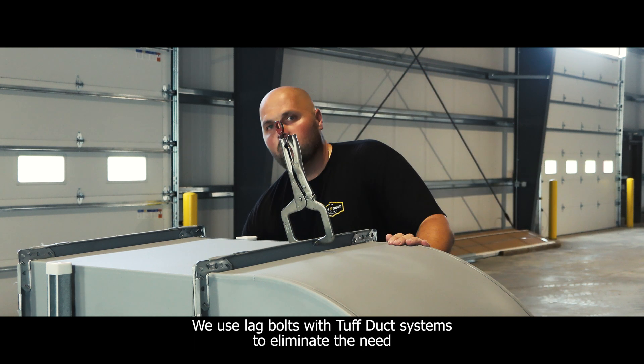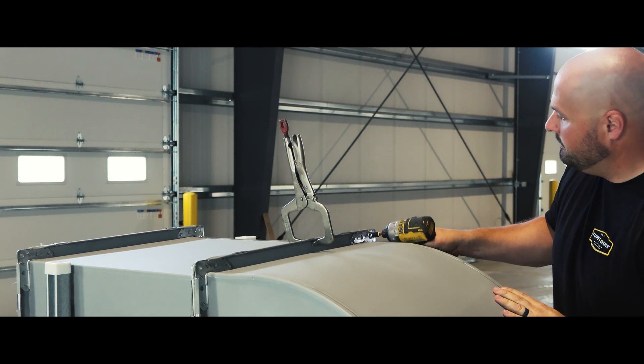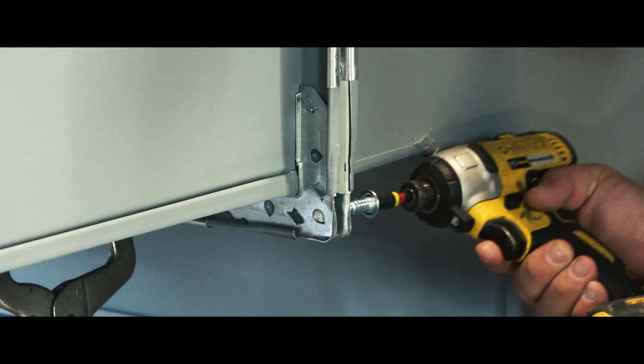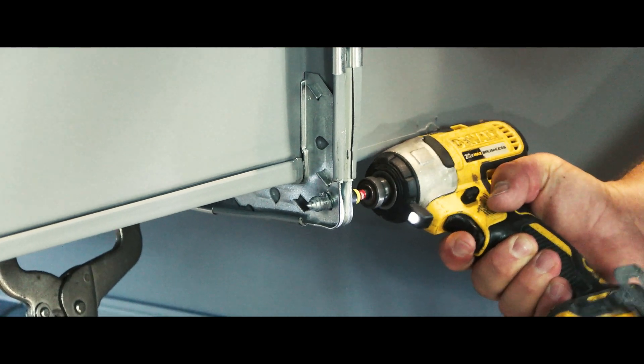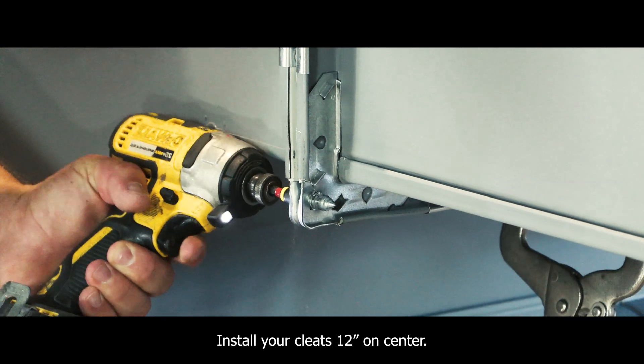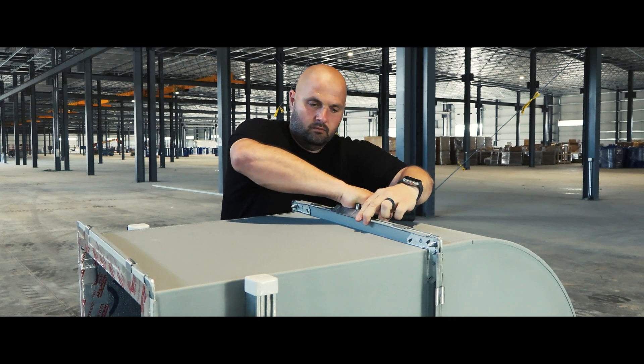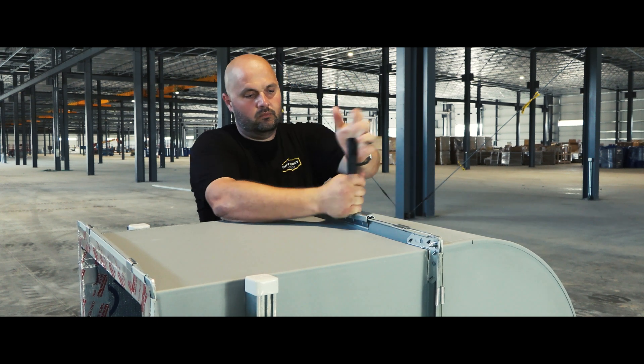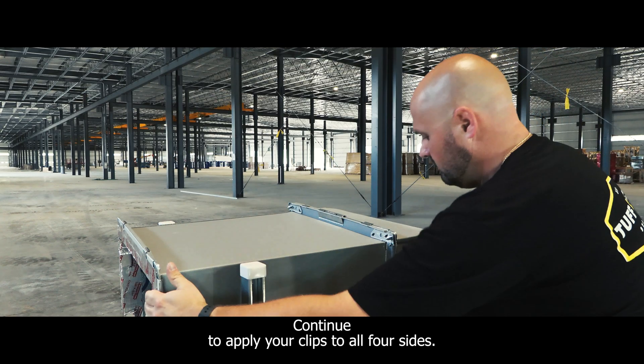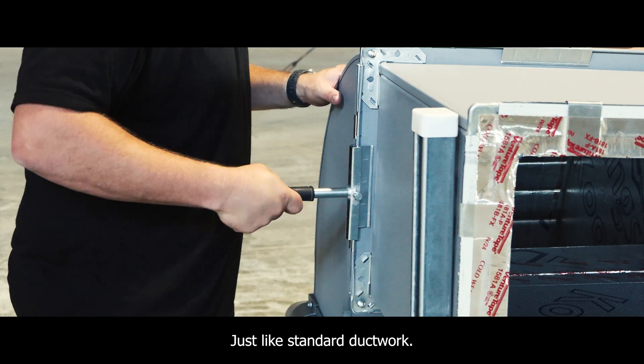With your duct in place using the Mighty Mount H-Frame, we can start doing our bolt connection. We use lag bolts with Tuff Duct systems to eliminate the need for your standard carriage bolt and nut. Install your cleats 12 inches on center, just like standard duct work. Continue to apply your clips to all four sides, remembering 12 inches on center is your standard clip spacing.